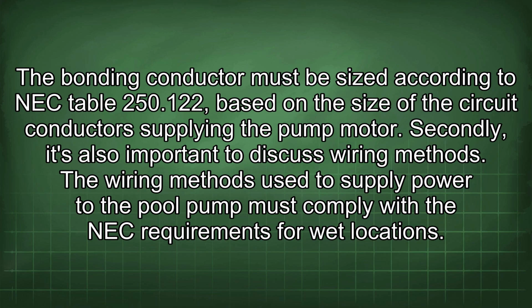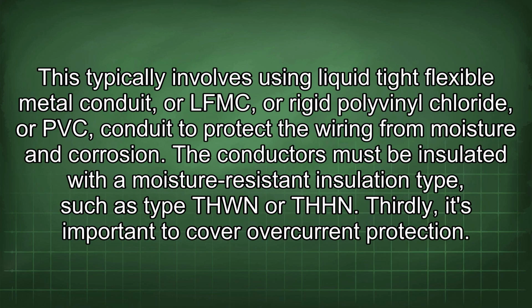Secondly, it's also important to discuss wiring methods. The wiring methods used to supply power to the pool pump must comply with the NEC requirements for wet locations. This typically involves using liquid-tight flexible metal conduit, or LFMC, or rigid polyvinyl chloride, or PVC conduit to protect the wiring from moisture and corrosion.